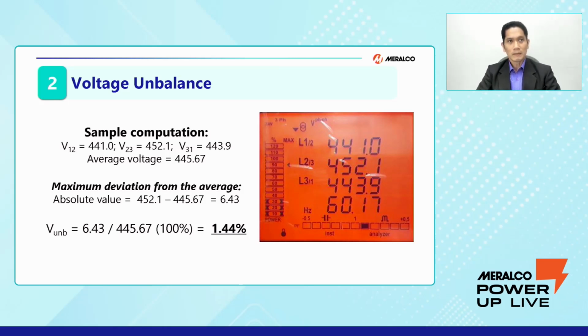But although there are sometimes that the unbalance is allowable, due to the overhead nature of the majority of our system, there are faults in our lines that will result in single phasing of our supply voltage. Thus, we recommend our end users to provide protections against single phasing to protect our three-phase motors.